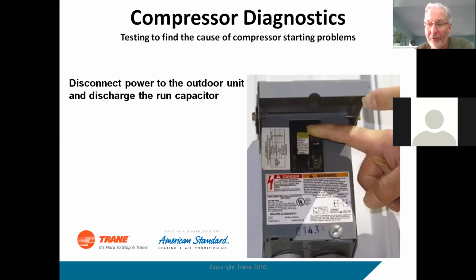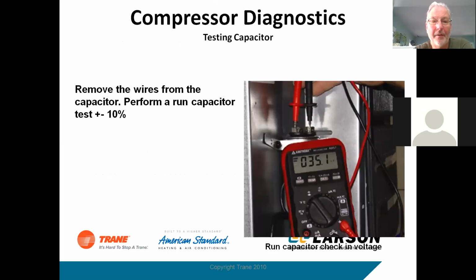Again, when you're checking capacitors, turn the power off, discharge the capacitor, check the capacitor out. Make sure it's plus or minus 10%, like it says on the capacitor.